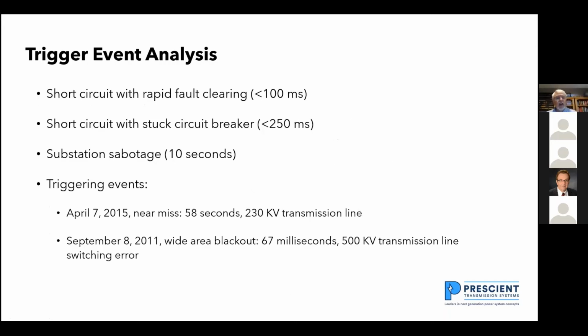We're looking at the timelines. Short circuits with rapid fault clearing take less than 100 milliseconds to clear the fault. If you get a short circuit where a circuit breaker sticks, one that fails to open on command, typically we're looking at somewhere around 250 milliseconds. And now the other thing we have to worry about today is substation sabotage. If the substation is sabotaged, it's probably going to take 10 seconds to clear the event off the grid. And we base these times on what we've seen happening on the system.